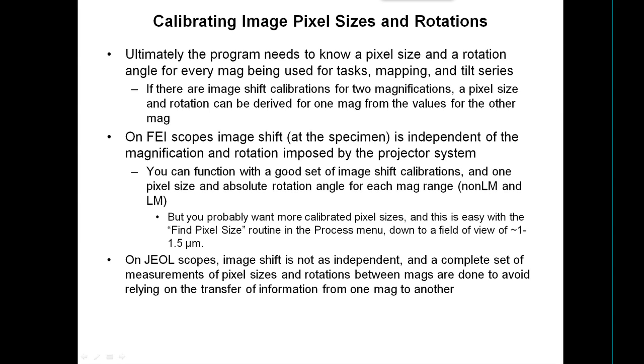The one tricky thing that really differs between the microscopes is calibrating image pixel sizes and rotations. For all the tasks, tilt series, and mapping we've shown, the program needs to know both the pixel size and the rotation angle of images on the camera for every magnification used. One nice thing is that if there are image shift calibrations at two magnifications and a pixel size and rotation for only one, it can derive pixel size or rotation for the other mag using the image shift calibrations.